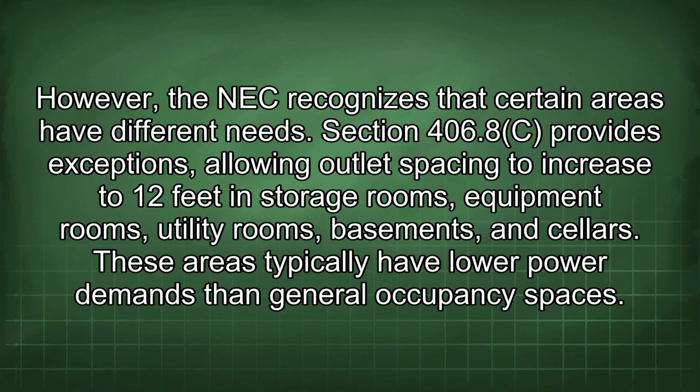However, the NEC recognizes that certain areas have different needs. Section 406.8(c) provides exceptions, allowing outlet spacing to increase to 12 feet in storage rooms, equipment rooms, utility rooms, basements, and cellars. These areas typically have lower power demands than general occupancy spaces.